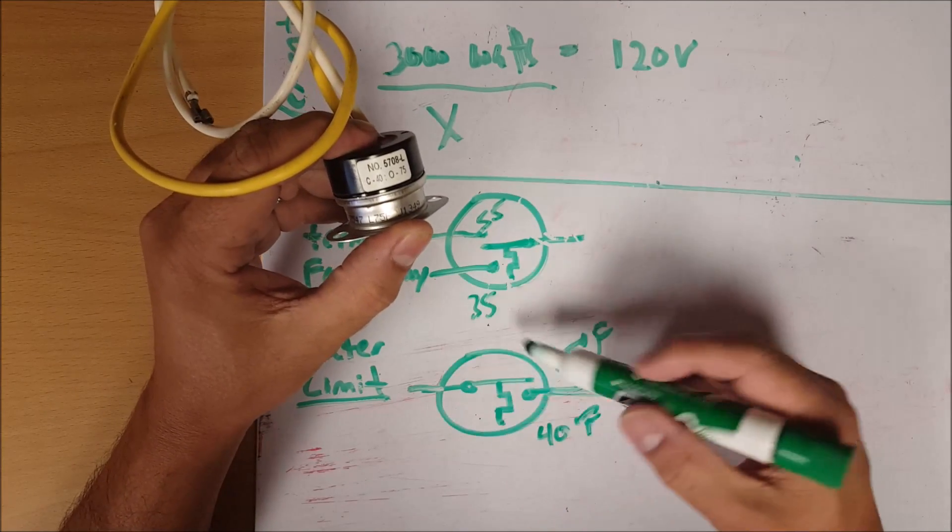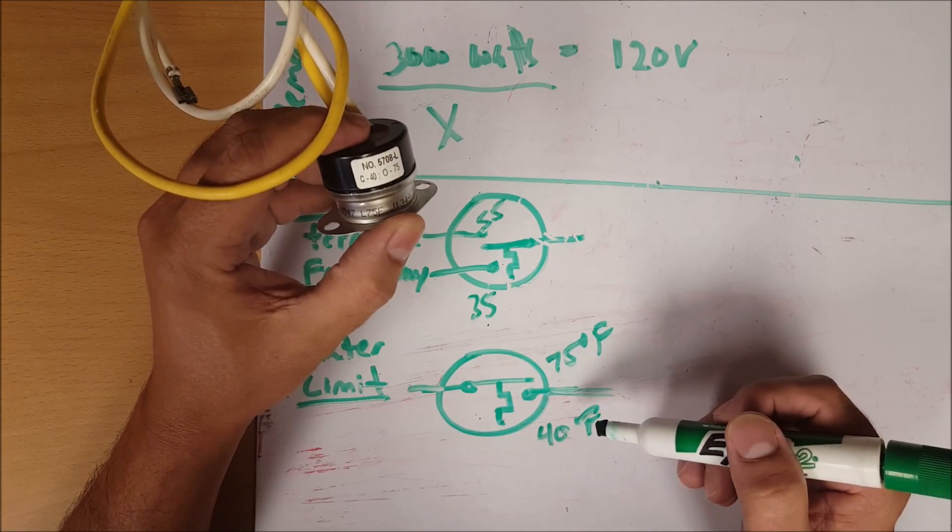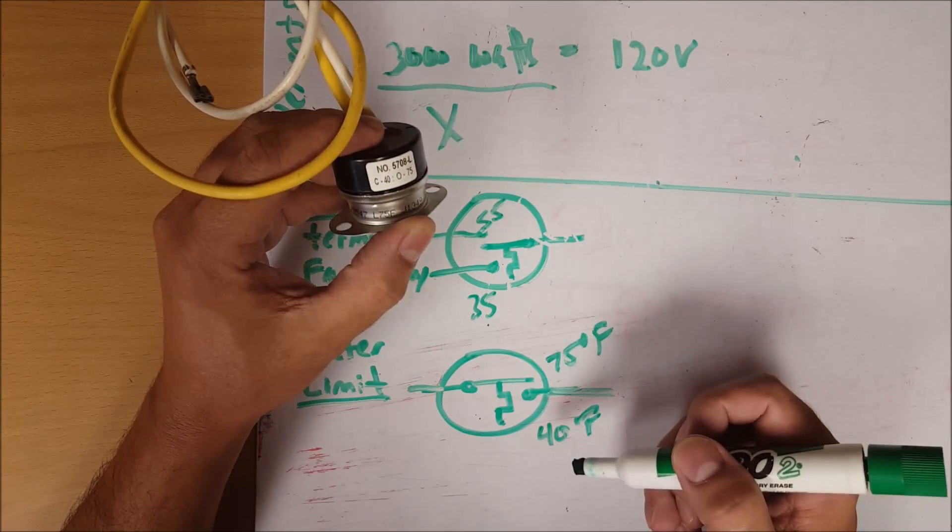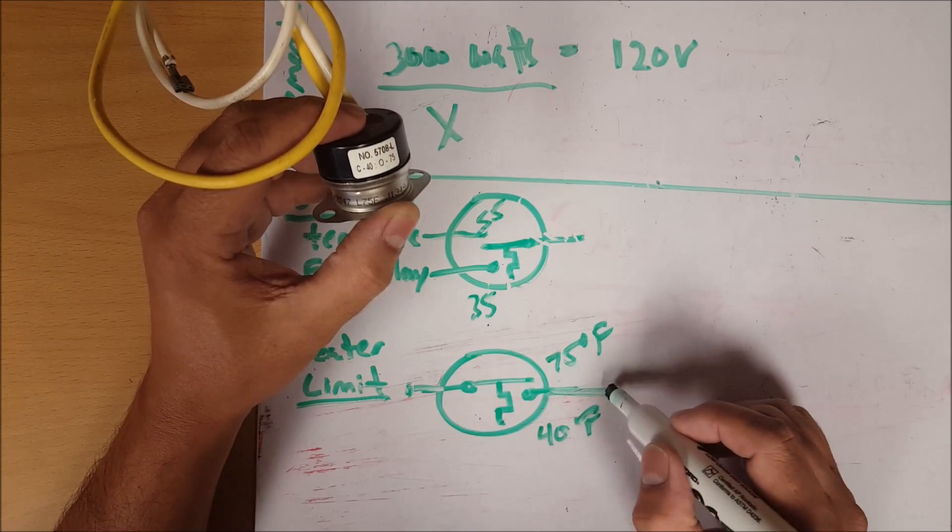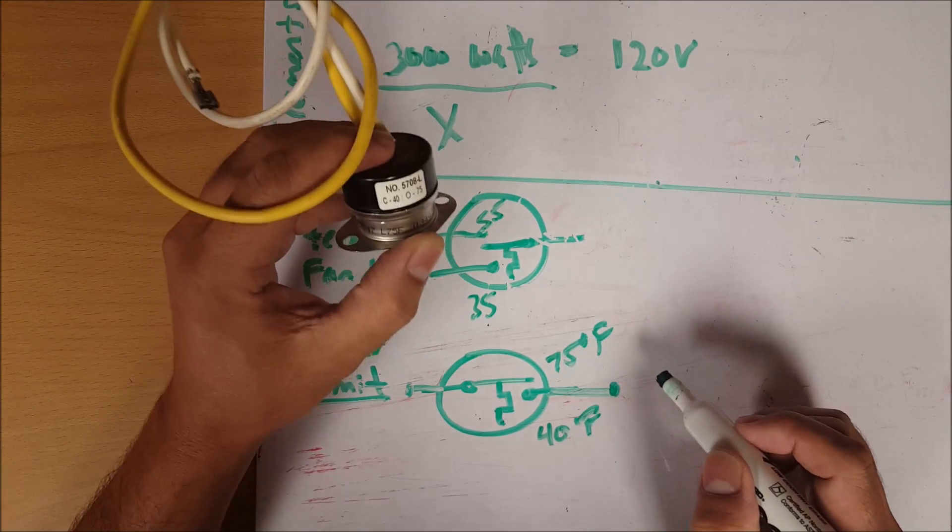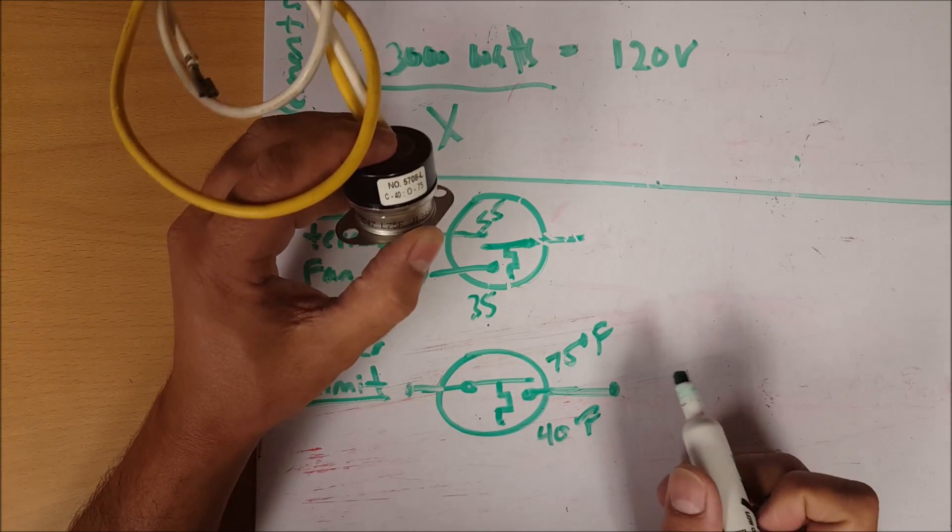So long as this thing is at 40 degrees, this switch should be closed. If the box temperature is at 40 degrees, that means this switch should already be closed. You could take an ohm meter or your continuity test and see if it's closed. If it's not closed, it's probably a bad switch.